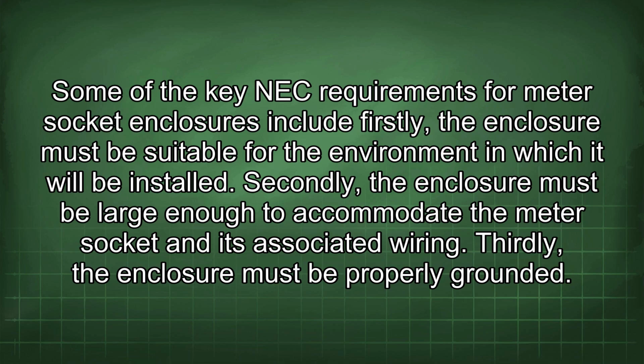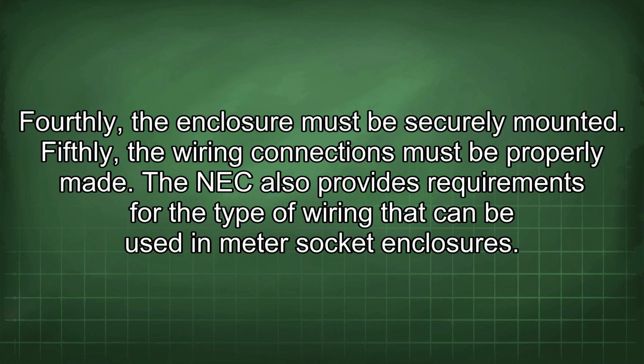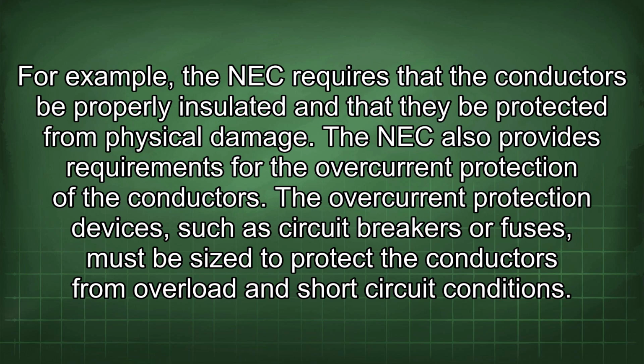Secondly, the enclosure must be large enough to accommodate a meter socket and its associated wiring. Thirdly, the enclosure must be properly grounded. Fourthly, the enclosure must be securely mounted. Fifthly, the wiring connections must be properly made. The NEC also provides requirements for the type of wiring that can be used in meter socket enclosures. For example, the NEC requires that the conductors be properly insulated and that they be protected from physical damage. The NEC also provides requirements for the overcurrent protection of the conductors.